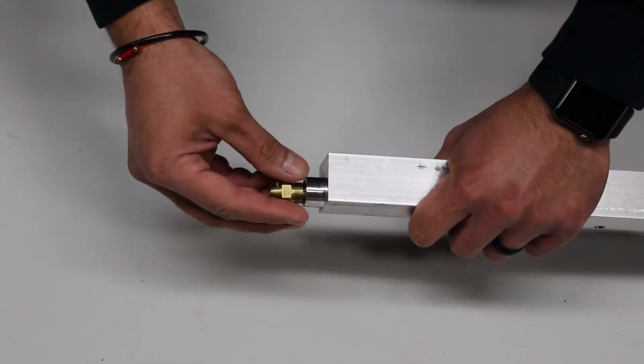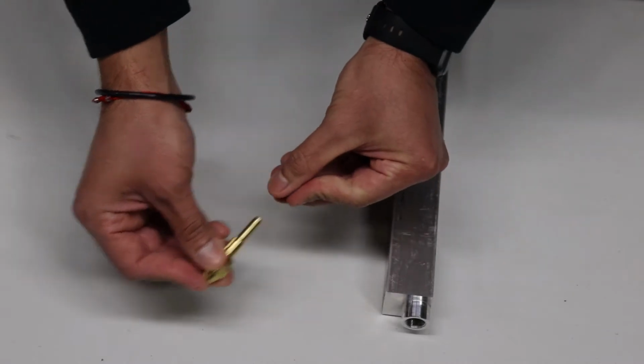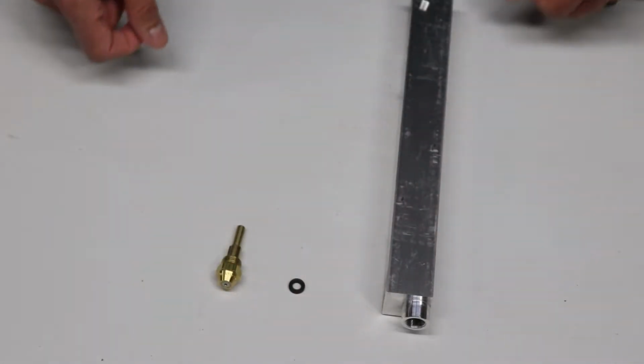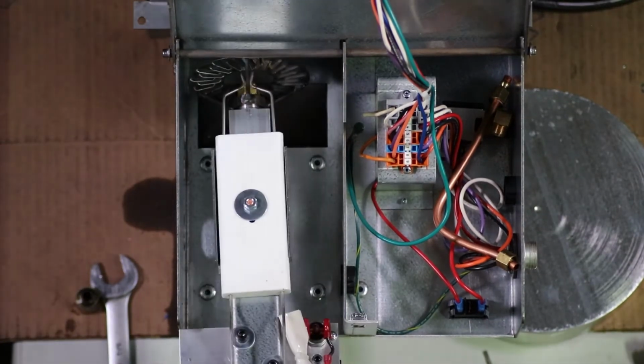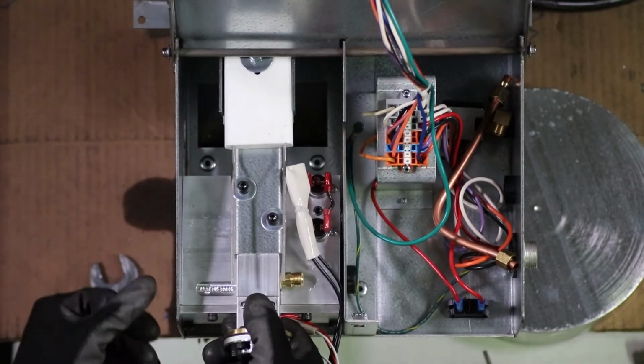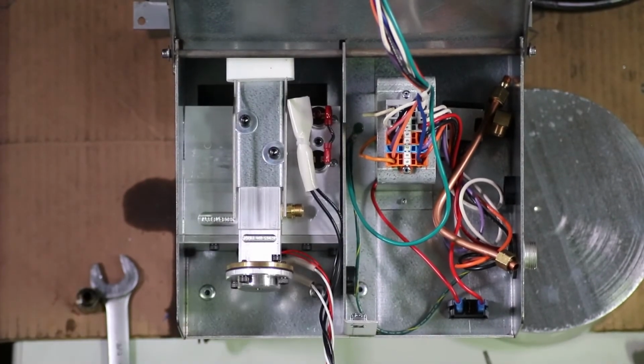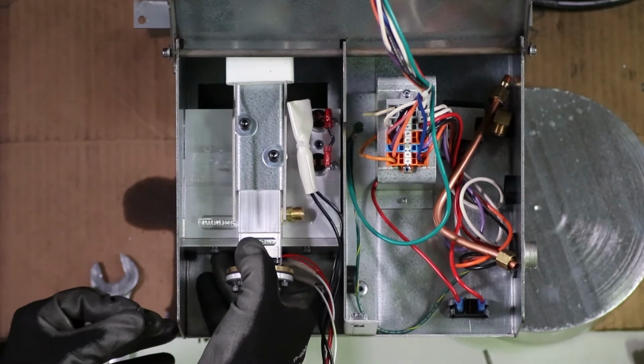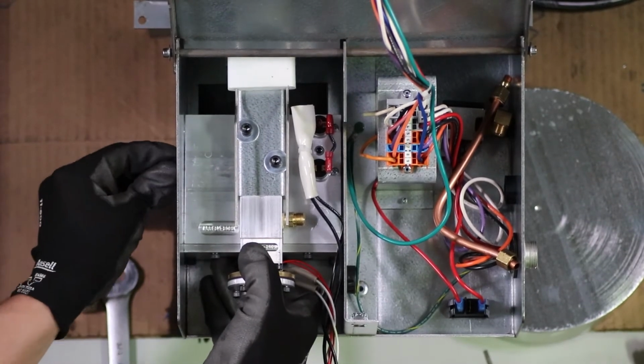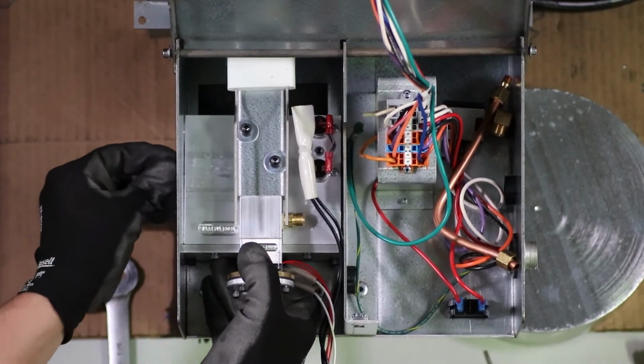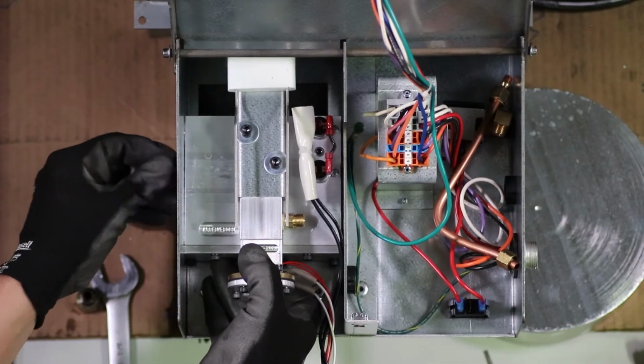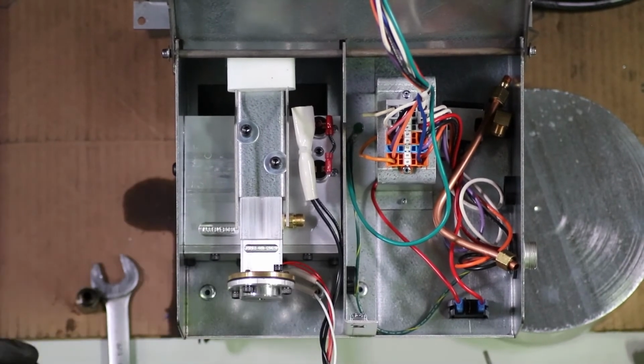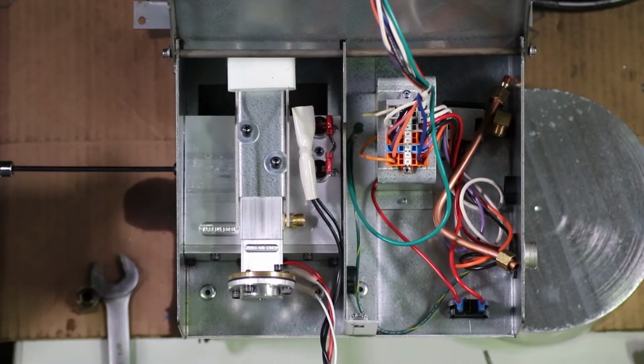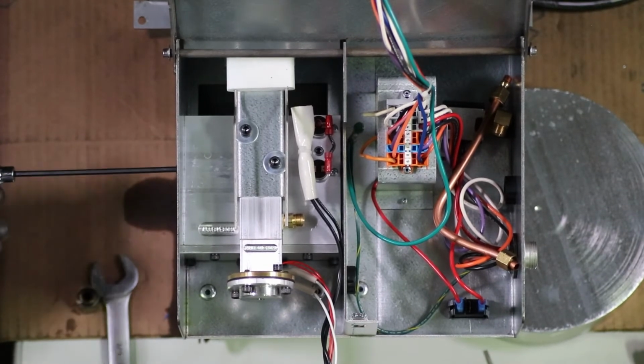If you have just replaced the nozzle and quad ring, remove them from the faulty preheater and save them for future maintenance. Lay the new preheater assembly into the burner chassis and loosely install the adjustment screw. Adjust the position of the preheater so that the assembly is oriented properly within the burner's flame tube. If your model came with a calibration tool inside the burner, use it to make the adjustment even easier. When the preheater assembly is correctly positioned, tighten the adjustment screw to fix it in place.